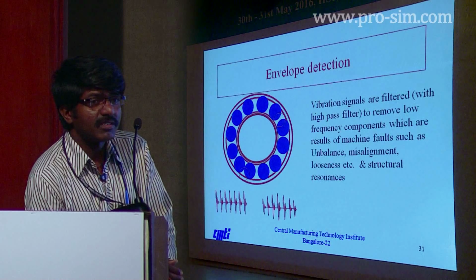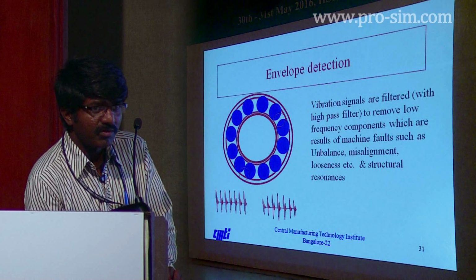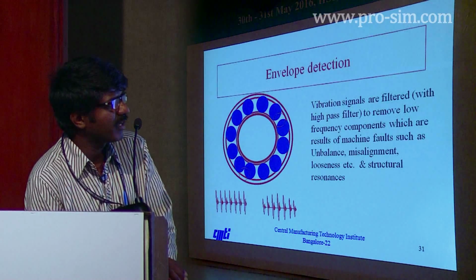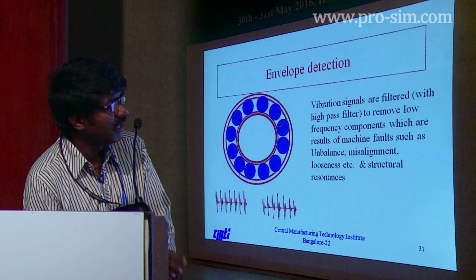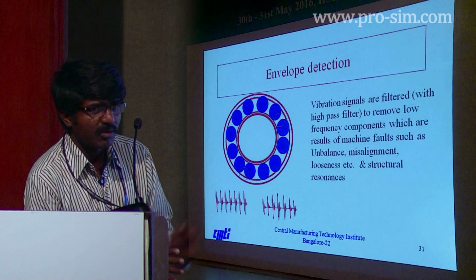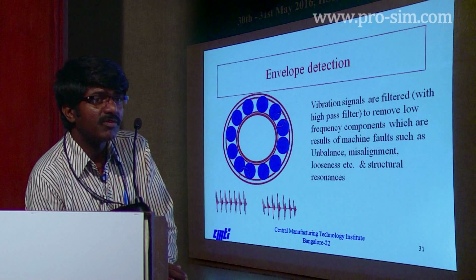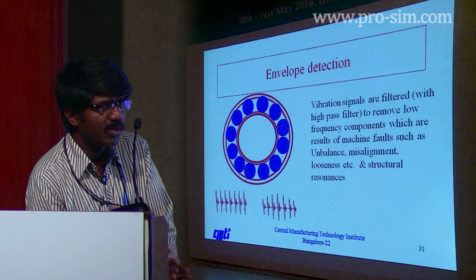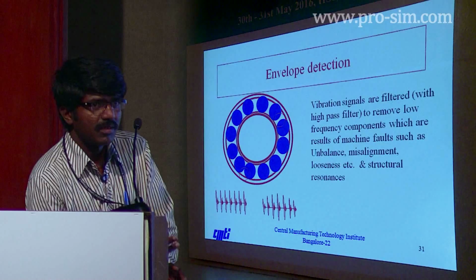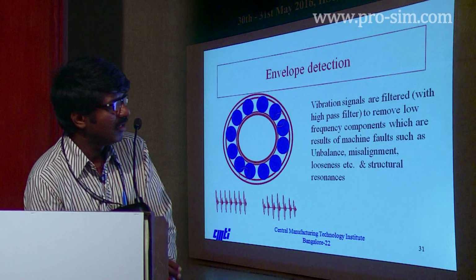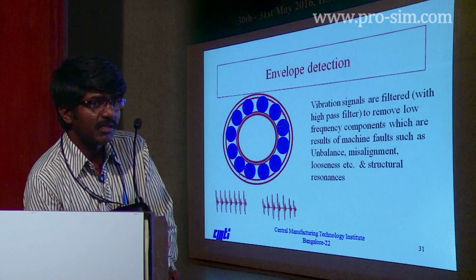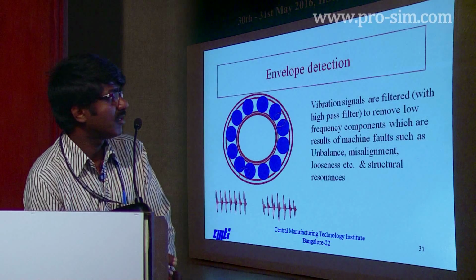These bearing defects are of low amplitude and high frequency components. These frequency components are masked by the high amplitude and low frequency components. So what we have to do is filter out these low frequency and high amplitude signals from the signal so that we get the bearing related fault frequencies. So that's what it does.